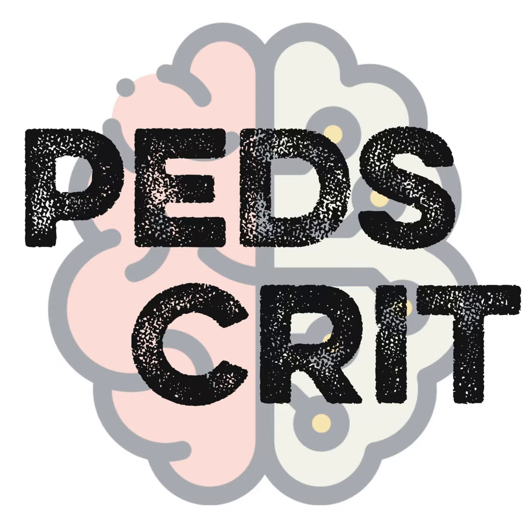One quick caveat about delivering other medications through continuous nebs through the VDR is, so this phasitron, this weird name device that sounds like it came out of some kid's cartoon, like the Transformers or something. So the phasitron, it's a sliding metal plate. And so if anything creates more friction, it interferes with how well that plate slides. And when that happens, the noise that the thing makes sounds different. So it's pretty loud, this phasitron. And if you walk into a room and you can't hear the VDR, then something's wrong with the device. And the phasitron is not working appropriately.